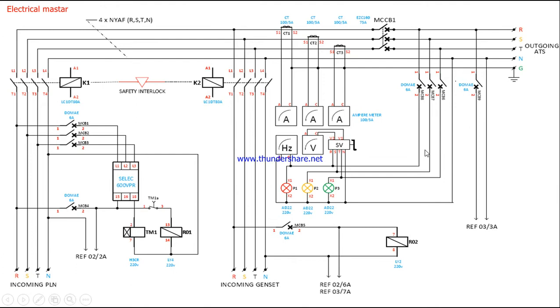Now we will see how the control supply activates K1 and K2. There is another MCB for an optional feature: if you want to charge the generator battery, you can take one supply from the load whenever the generator is off. That supply is connected to the diesel generator battery through a converter — from AC phase supply to a rectifier, changing it to 24V or 12V DC, which is then connected to the generator battery.